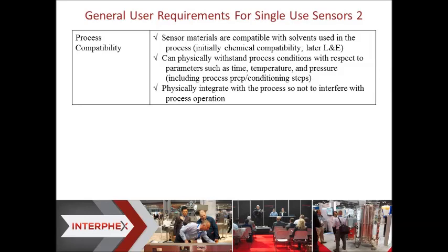As far as process compatibility, before even doing anything like leachables and extractables, you want to make sure you have general chemical compatibility with any solvent used in the process. You have to make sure it will withstand the process conditions such as time and temperature. It may not need to measure across all those ranges. For instance, a lot of sensors can be autoclaved, but they won't function at those high temperatures, but they will function after. And you want the sensor to physically integrate into the process so it doesn't interfere. You want a seamless integration.